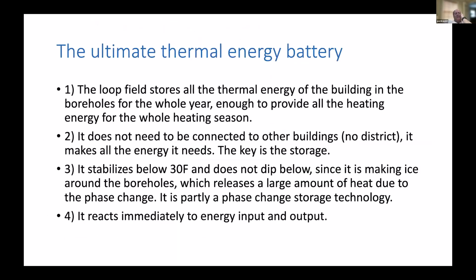So this is actually a great thermal battery. We're putting heat in. This is not new. What is new is that we have really, really good means now to quantitate this and understand the flow there. The loop field actually stores all the energy of the building in the boreholes for the whole year, and it's enough to provide all the heating needs and all the thermal energy for the whole heating season.